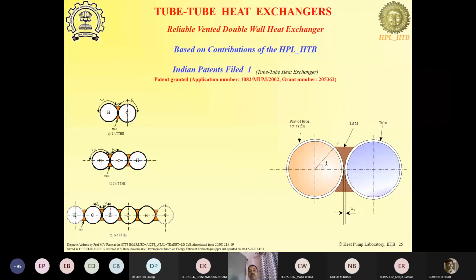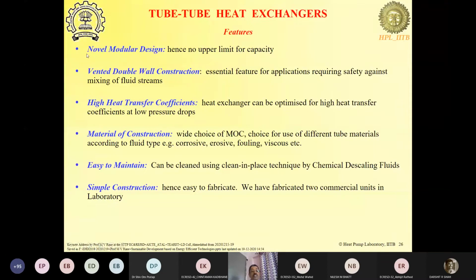Okay. So this is the tube heat exchanger. We had talked about the 2-tube configuration. Then you can have a 3-tube configuration, and you can have more tubes also in this particular case. Now, the main features of these are that they are modular in nature, so there is no lower or upper limit in capacity. We have done a small heat exchanger of 0.5 ton capacity, and we have done up to 270 ton capacity also. And if somebody asks us to do a 3000 also, we will not hesitate in designing and deploying them.